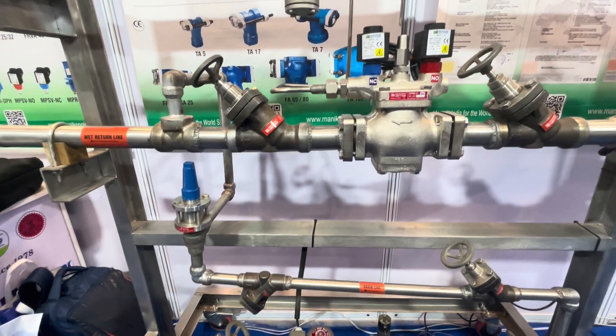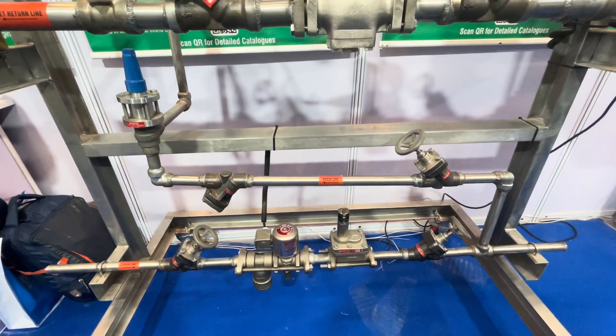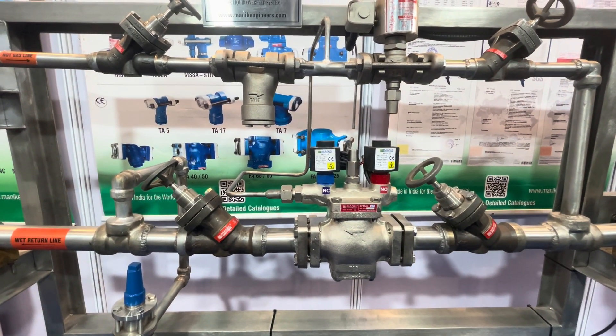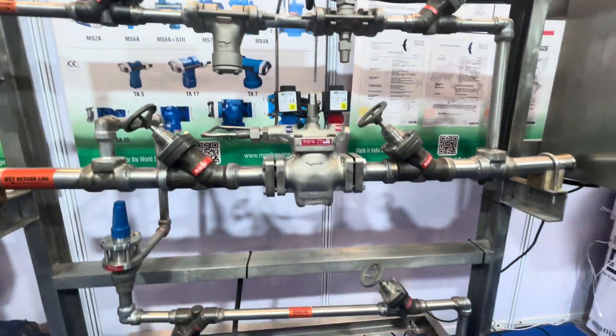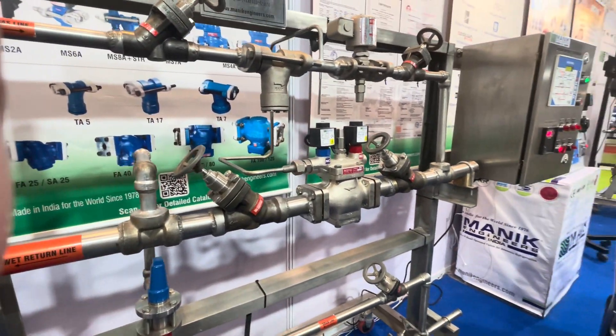During the hot gas defrosting, the liquid line solenoid valve will be closed, and then after pump-down the hot gas valve will be enabled, the line valve will be closed, and then the hot gas will start. We'll have a wet return line system — this is how the complete cycle works.